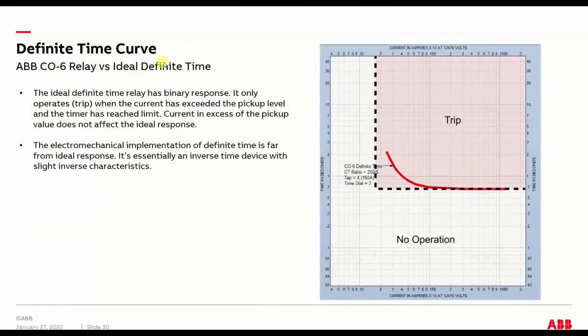Here's an explanation of the last important one, which is definite time. Definite time means that if the relay picks up, it times to a certain preset number, and then it trips. The historical stuff, and some stuff that's still around today, is not exactly that; it's more this red curve than the on-off. So just be wary of that. The definite time is used for things like that 51 time delay, and a lot of functions that are not involved with current, like overvoltage. It's basically hit a pickup value, wait a certain amount of time, preset time, and then trip or not trip.